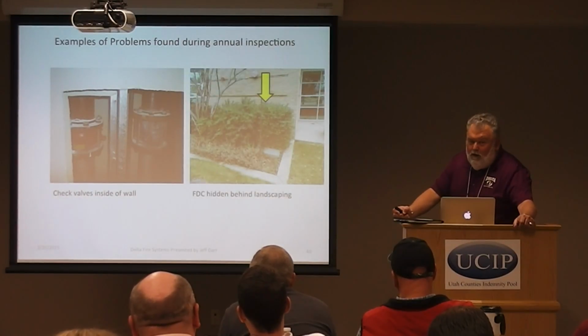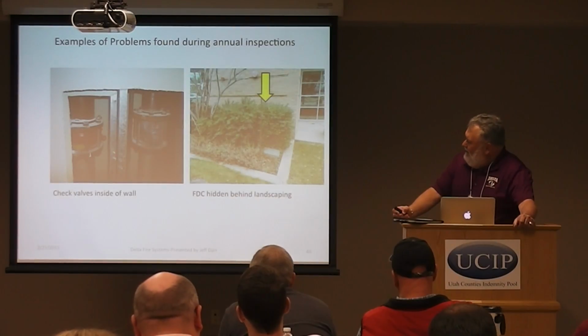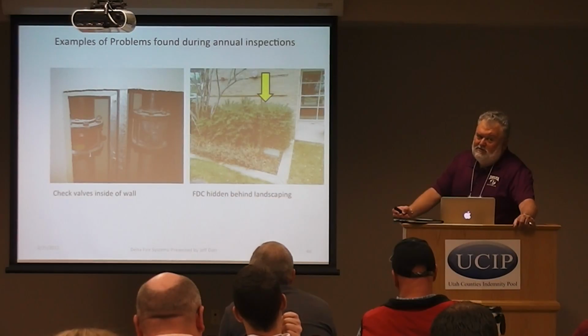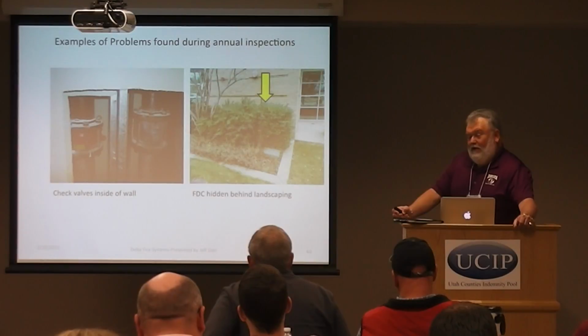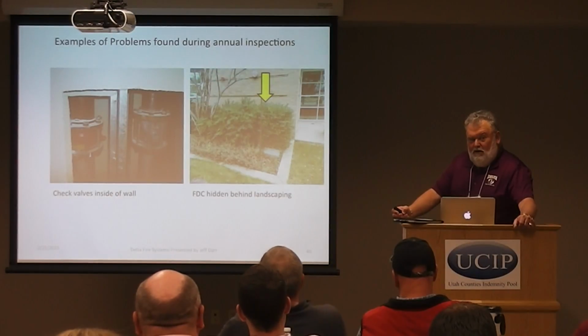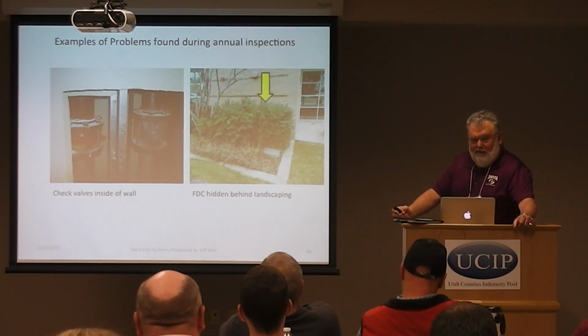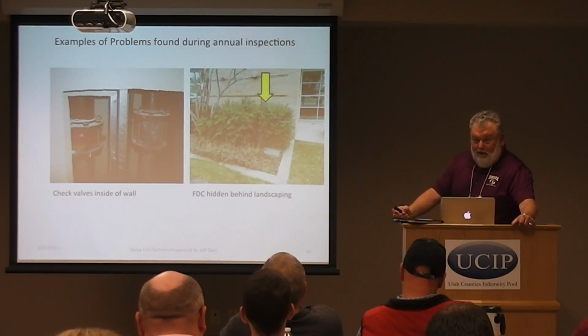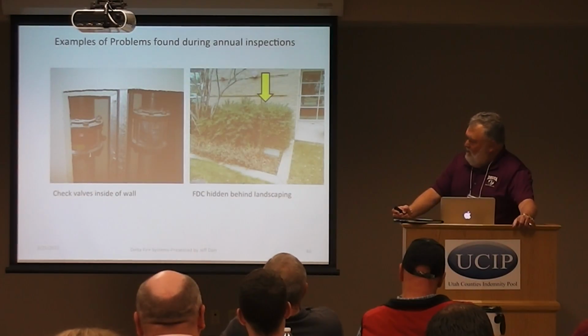And it's required that valves be accessible. And I get a kick out of the one on the left here. When this system was installed initially, I'm sure they were accessible. Over a period of time, they'd done a remodel, and the contractor thought, well, we'll cover those ugly valves up for the owner and make it a nice wall. The only problem is, it made it so nice that we couldn't drain the systems or anything else.